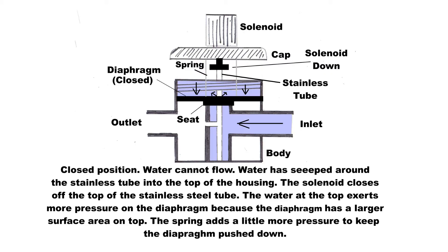Water has seeped around the stainless tube into the top of the housing. The solenoid closes off the top of the stainless steel tube. The water at the top exerts more pressure on the diaphragm because the diaphragm has a larger surface area on top. The spring adds a little more pressure to keep the diaphragm pushed down.